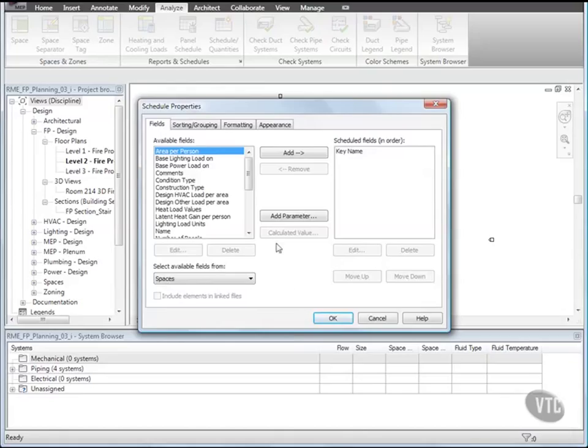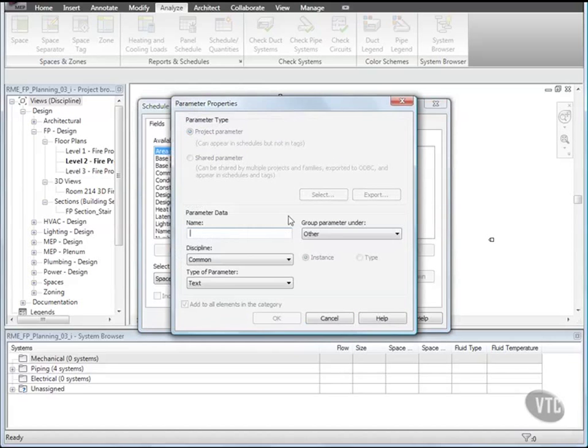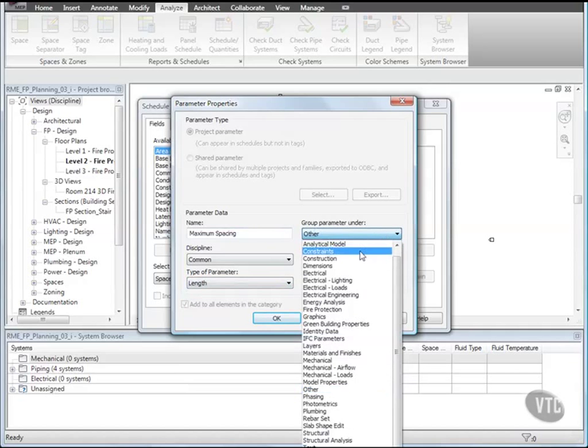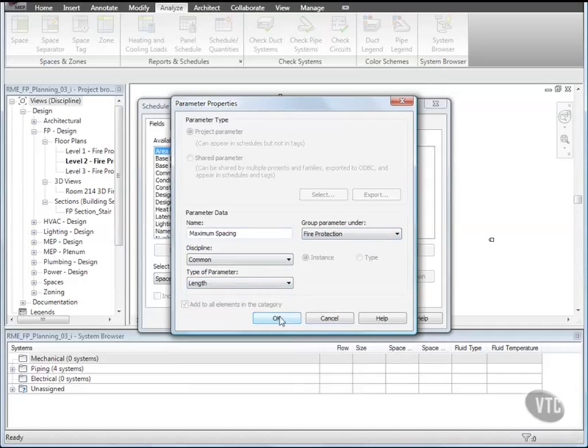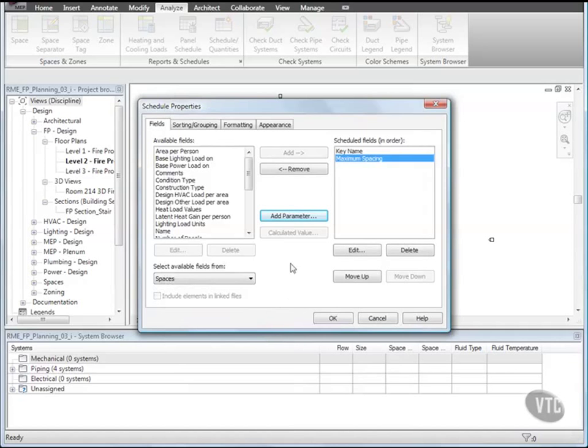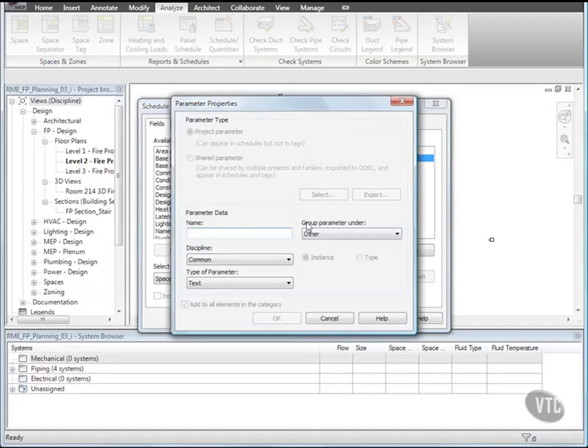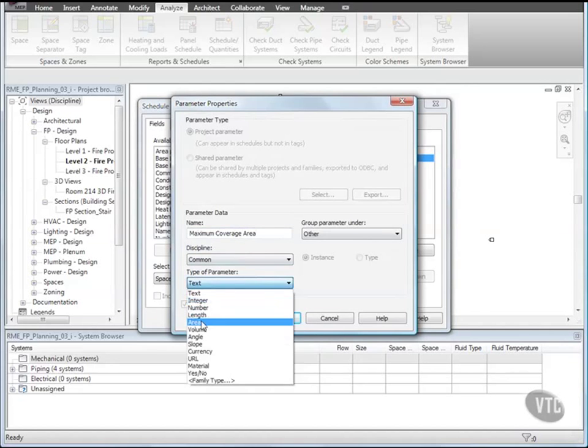In the Schedule Properties dialog, click Add Parameter. In the Parameter Properties dialog, for Name enter Maximum Spacing, and for Type of Parameter select Length, and for Group Parameter Under select Fire Protection. And click OK. Using the same method, create a parameter named Maximum Coverage Area that is an Area type grouped under Fire Protection.